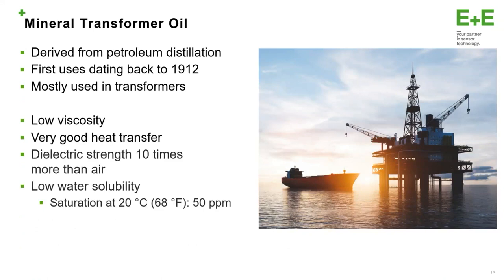Consider that a power transformer for generation step-up can contain 80,000 liters of oil or more. For this quantity of oil, we are talking about a price range of 200,000 euros for mineral oil. So the mineral transformer oil is the insulation fluid most used in this application. The mineral oil is derived from petroleum distillation — a material which has been present on the planet for millions of years. The properties of mineral oil include low viscosity, very good heat transfer, electric strength which is 10 times better than air, and very low water solubility — at just 20 degrees Celsius, this oil can contain only 50 ppm of water.